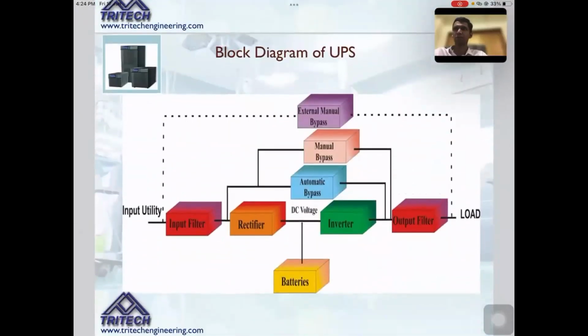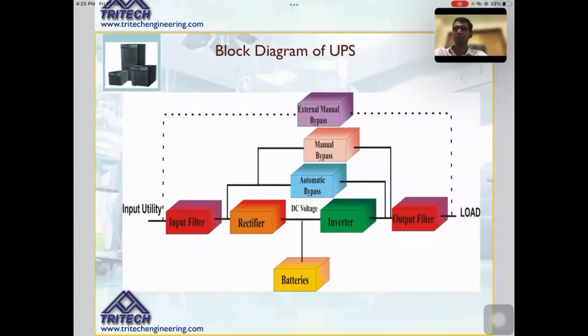Again, if you look at the block diagram of a UPS, you have an input power supply with the filter, then the rectifier and batteries, the inverter, and again the converter to the load. So basically, you have this AC to DC converter, which charges the battery, and from the battery to the inverter and back to the AC supply. In this scenario, you normally have a normal line, and the batteries are permanently connected, with on and off done by digital systems. And again, there is an automatic bypass using static bypass switches, and also a manual bypass. If the static bypass fails, you can have a manual bypass also. So most of the UPS systems are in this format, whether conventional or modular UPS systems.